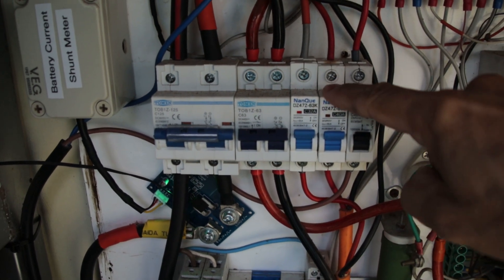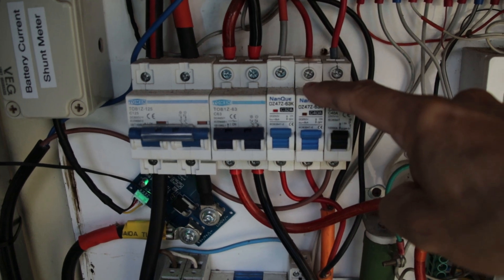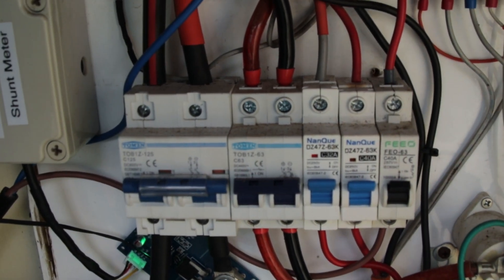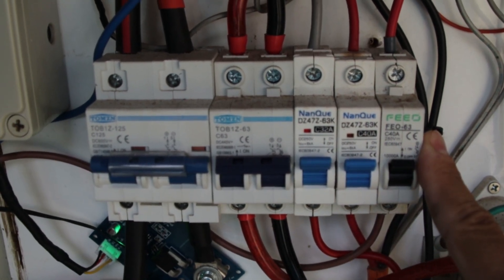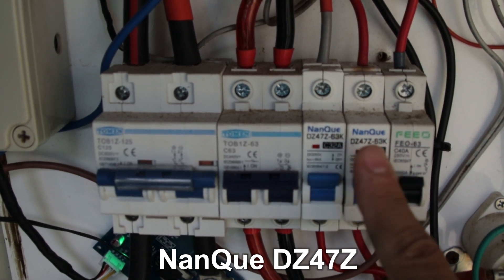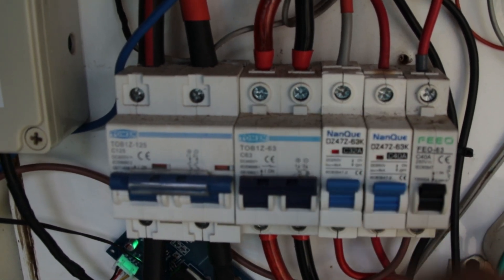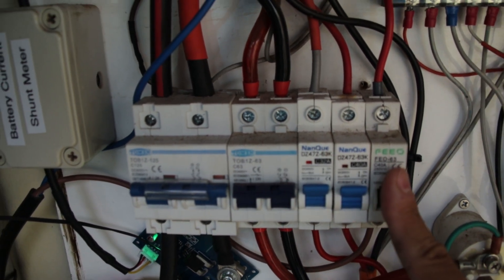Again, a DC breaker — this is a 40 amp breaker for a 25 amp charger — internally disconnected. You might remember that about six months ago I replaced all this breaker bank with new NanQue non-polarized breakers. Now you can see there is no NanQue left here anymore except these two, and this one has also failed.